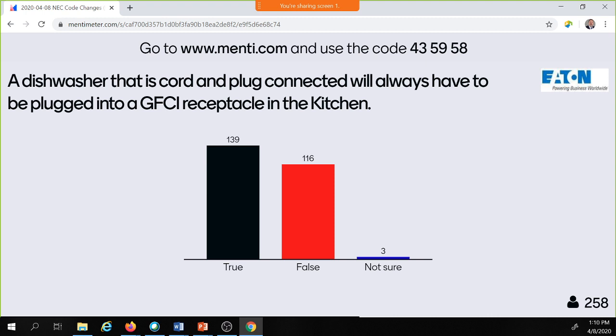Remember, 422 is on appliances, and 422 has dishwashers in it, and it tells us that you can put it within the branch circuit overcurrent device. You can put a device or outlet within the supply circuit. You can have it as an integral part of the attachment plug. You can have it within the supply cord, not more than 12 inches from the attachment plug, or you can have it factory installed with the appliance if they make it that way. So, no, we don't necessarily always have to have it plugged into a GFCI receptacle.